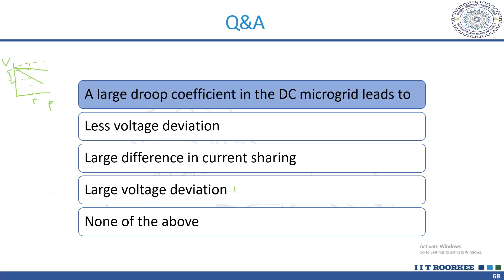Then coming to week 7: a large droop coefficient in a DC microgrid leads to less voltage deviation, large difference in current sharing, large voltage deviation, or none of the above. Yes, basically this is your V versus P, and for the same power sharing, the difference in voltage will be large. So it will be large voltage deviation.